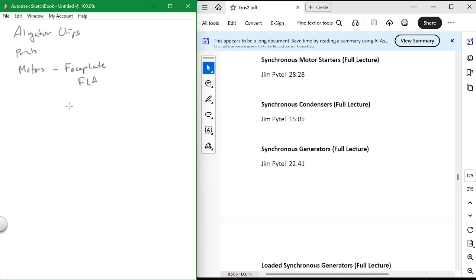Okay? So you may end up with a 25 instead of a 20, or a 15 instead of a 12, or a 12 instead of a 15. It can vary. And in that case, what do you do? You don't go back and complain to the people and say, no, I have a 15 on my drawing, and you've got to change that motor out to a 15. No, you have to match the breaker and the overloads to the actual motor out in the field. So that's your first step. And what does this do for you?